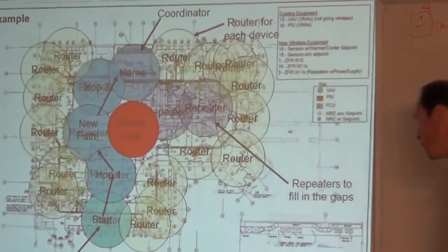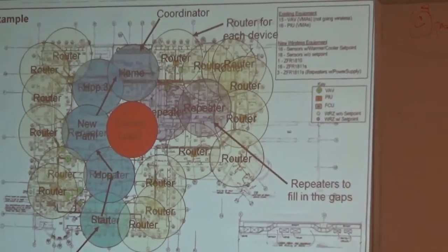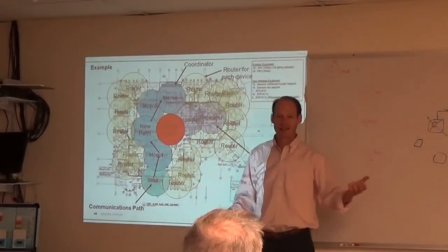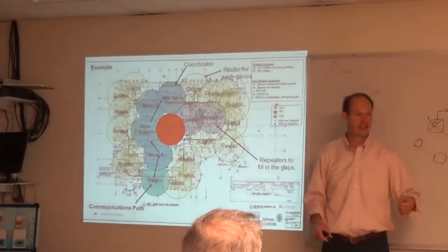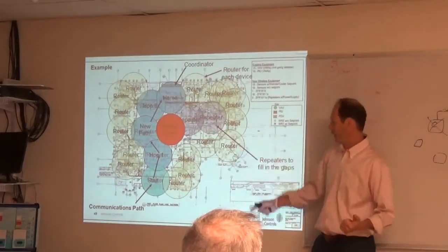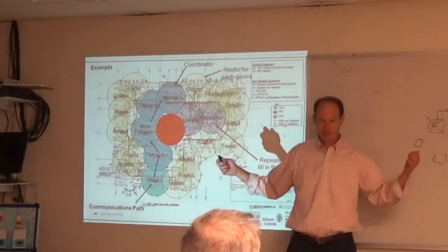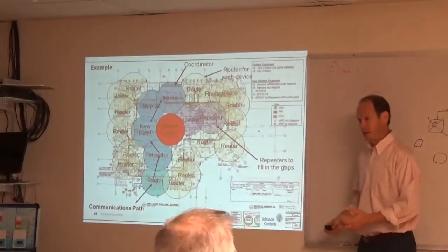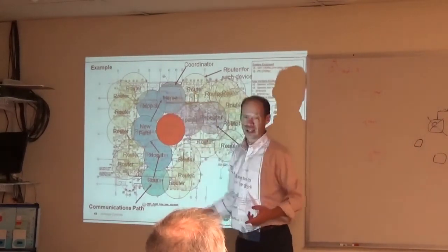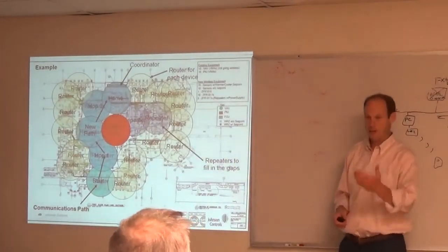So this wireless stuff is really good for space temperature. If I'm doing process control or anything like that, not so good, right? Because this process right here could take 5 to 7 minutes to reform. So if I need a temperature value every minute, I'm not getting it, that's not the right way to go. Controllers are still working, it's just that I don't have that value to go back to the supervisory device, okay? So the controller's not down, but if I have a trend that I have to get every minute, if this guy goes down and this takes 5 minutes, I've lost 5 minutes worth of trend values. So it's really made for space temperature, not for process control.